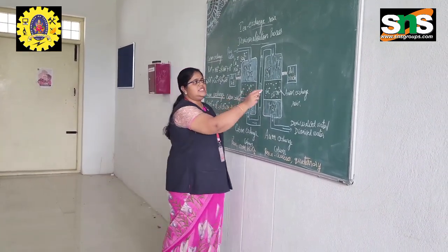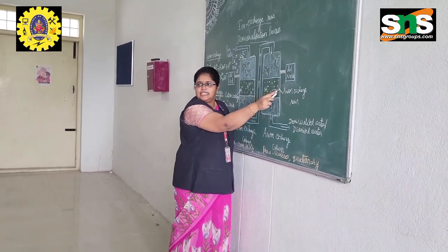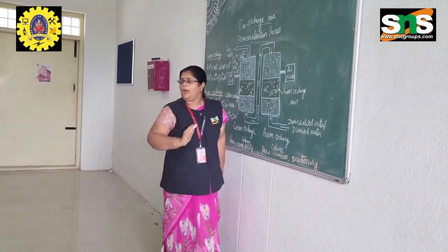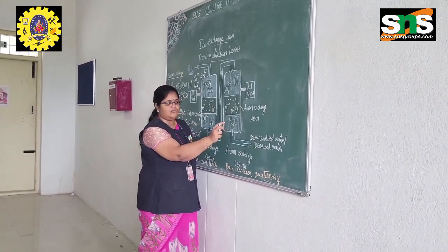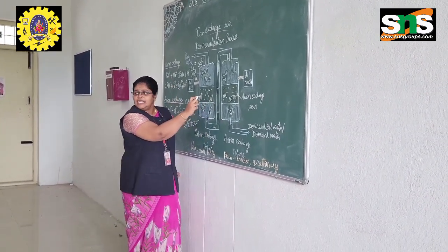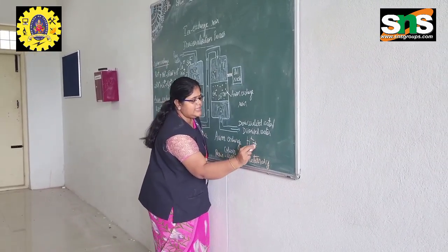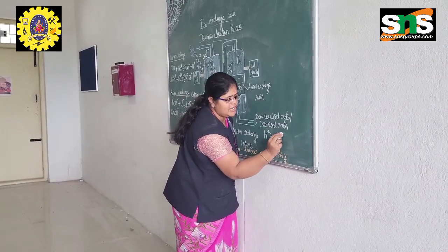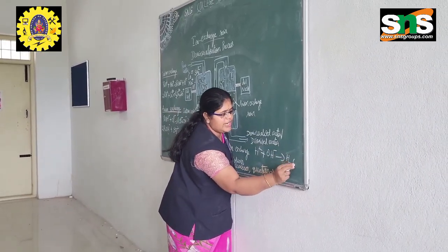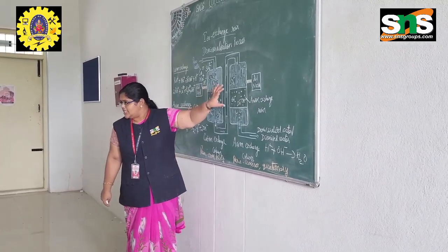Okay, so this sulfate ion and chloride ion are being substituted by the OH minus ion. The water that is coming out of this is exchanged with H plus ion in the cation exchanger, and in the anion exchanger it is exchanged with OH minus ion, and finally you get H2O coming out of this chamber.